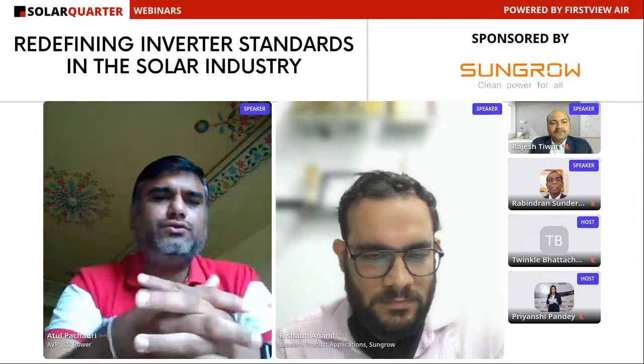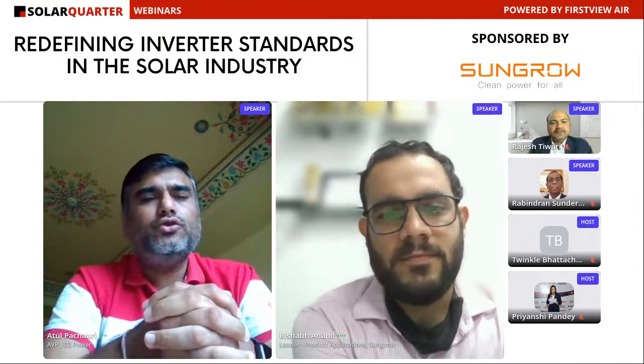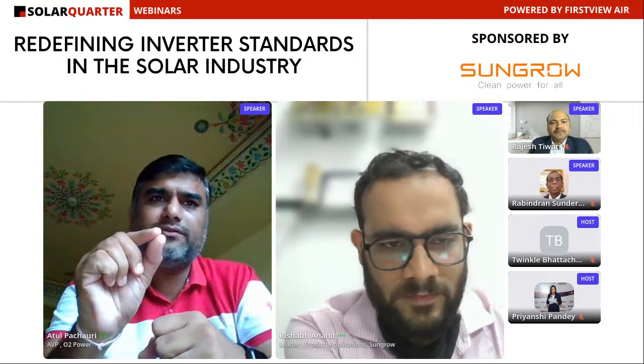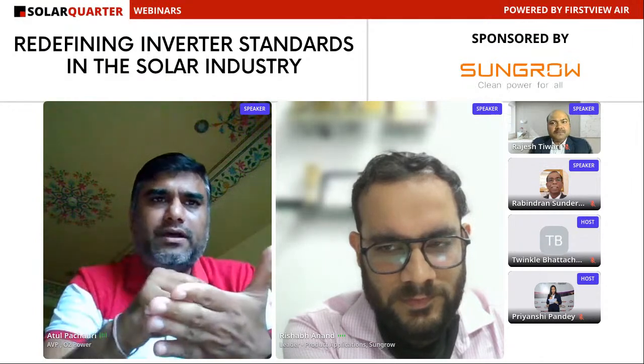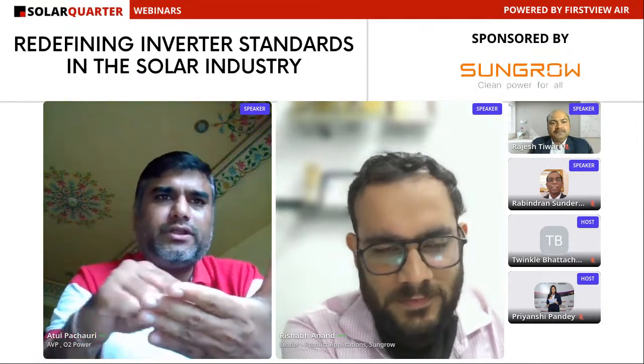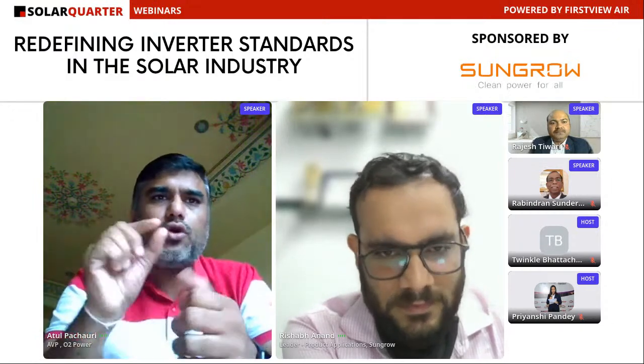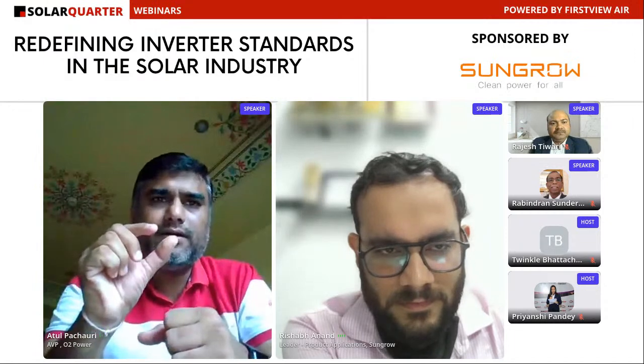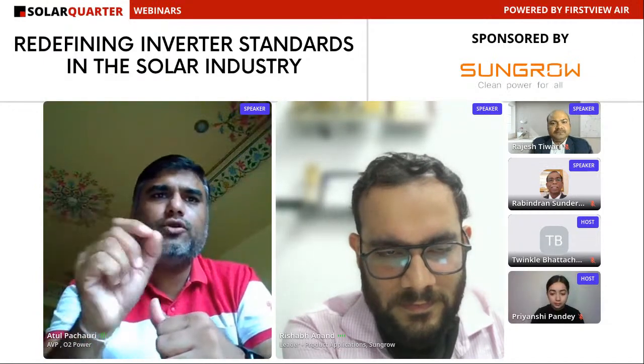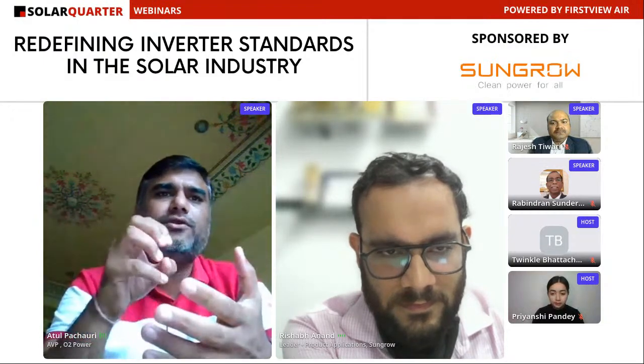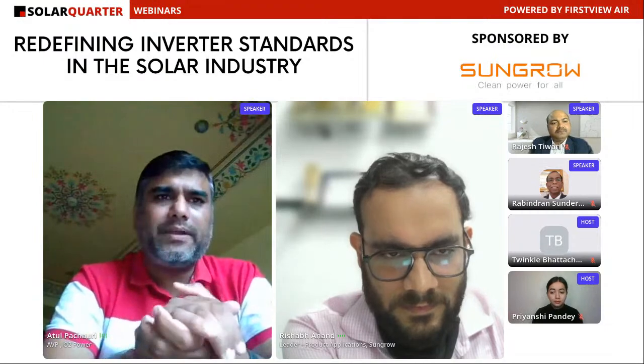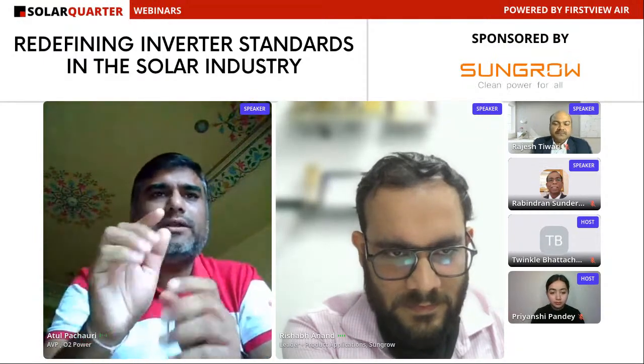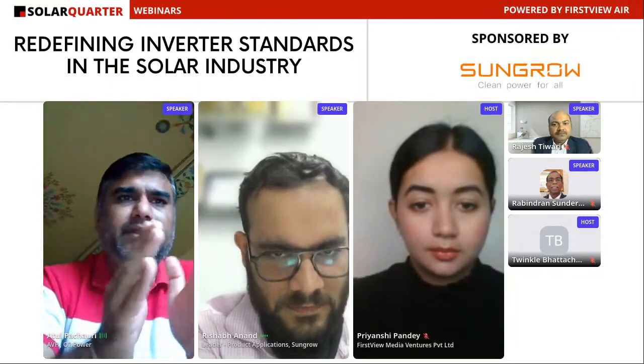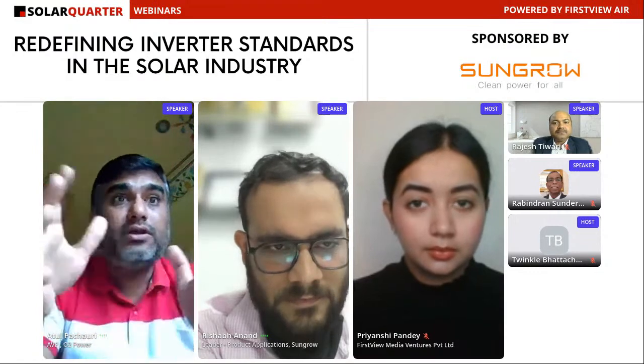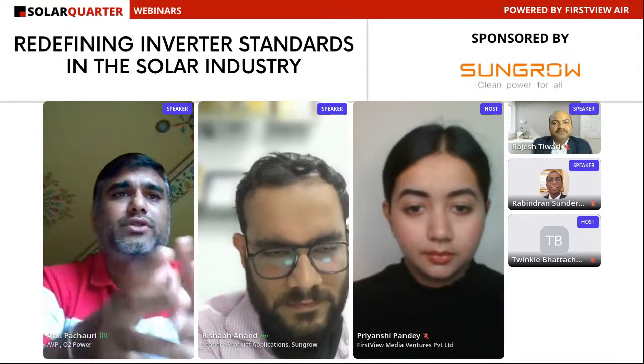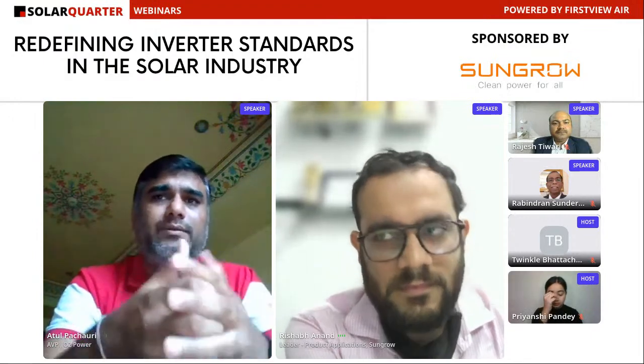But I would suggest you, or your technical team, provide a feedback mechanism indicating that the inverter is going into degradation mode. As we already give address registers for power, reactive power, voltage control, everything available on the Modbus platform, you should similarly be able to give an indication that the inverter is going into degradation mode due to, say, heat sink temperature, IGBT temperature, ambient temperature, or whatever degradation pattern your algorithm follows. This way people get alarmed that their inverter is degrading, and they can go clean the filter or check what's happening with that particular inverter, so they get maximum generation from the available resources.